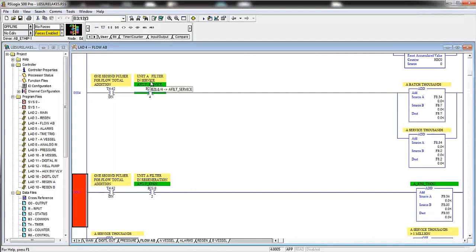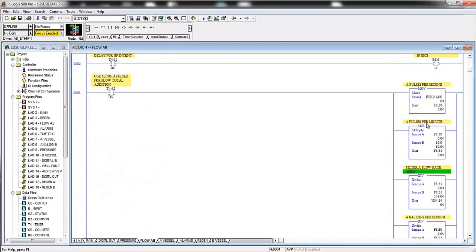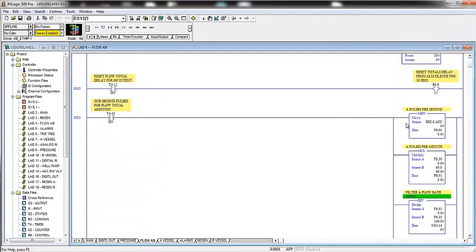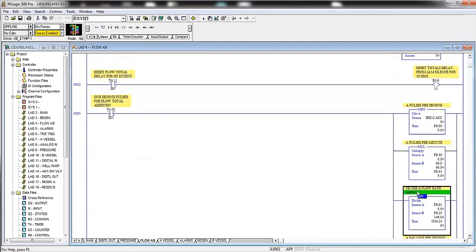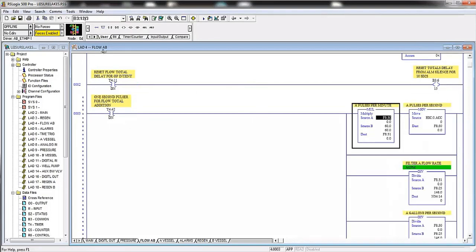So if you don't take anything else out of this lecture, the one thing you can't forget from here going forward, this is the one thing that makes ladder logic make sense: what you see on the left are conditions. What you see on the right are actions. And for each branch, you have one action. If we want multiple actions to come out of this rung, we have to put each action on a separate branch. What we cannot have is two actions on the same branch.